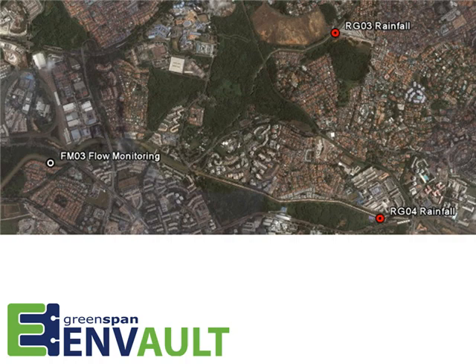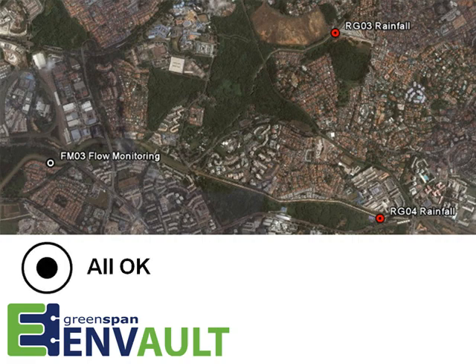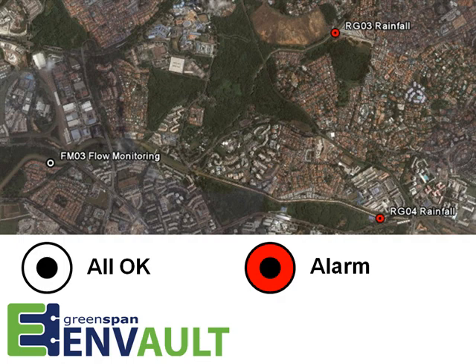You may have noticed the color of the dots were different. The two rainfall stations are red. In general a dot will be white, meaning all OK. For the rainfall stations, the red dot tells you that all is not OK — this is the alarm state. The icon will automatically change to red when an alarm is active from a site. In this case, the rainfall stations had received a high amount of rain in the last 24 hours — an alarm condition. Alarming comes with all the features of mobile phone alerts, emails, escalation, and redirection, because of the SCADA engine running behind the scenes.